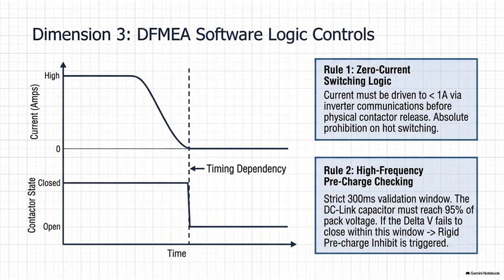The logic assumes something is profoundly, dangerously wrong. Perhaps the physical resistor has burned out and increased its resistance, or perhaps there is a massive short circuit somewhere in the high-voltage architecture that is actively draining the power as fast as the pre-charge circuit can supply it. So it panics. Whatever the underlying cause, the processor determines the environment is not safe for high current. Because if the software were to foolishly close the main switch while the capacitor was only at 50%, the resulting inrush current would still be massive enough to overwhelm the magnetic blowouts and weld the contacts solid. Exactly that. So when the 300 millisecond mathematical check fails, the system rigidly locks the main contactor in the open position. It completely refuses to proceed with the startup sequence.